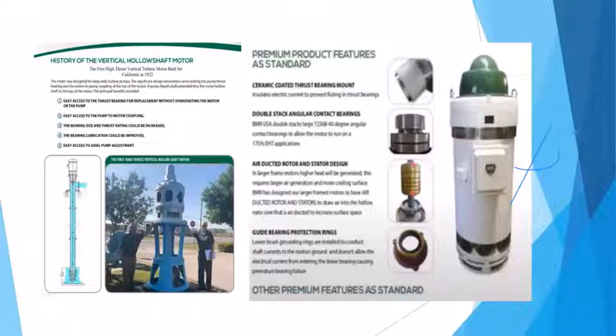And so we've got a lot of heat factor. So you don't want these motors to get hot. And what he was talking about is the difference between classes of insulation. Early on in the 60s, B insulation was kind of the norm. We didn't have a lot of the new ceramics and things that we have today. Then they went to class F, then they went to class H. Well, what they've done then is they've shrunk it all so that the magnetism creates higher heat in those coils, and that doesn't create extended life.